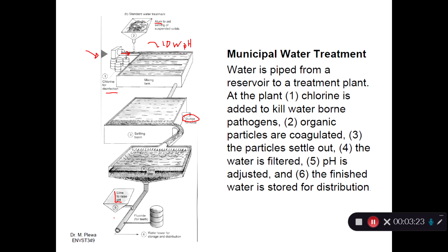And this is part of what happened in Flint, Michigan. As you may or may not be aware, in Flint, Michigan, they changed the source of their drinking water because they wanted to save money. The new source, as I understand it, was a little bit more acidic. So they sent that more acidic water out through their pipes. That caused the pipes to corrode. The pipes had lead in them, and so that released lead. If they had stayed with the old source of drinking water and the old process, they would not have corroded the pipes. They would not have created the lead issue.